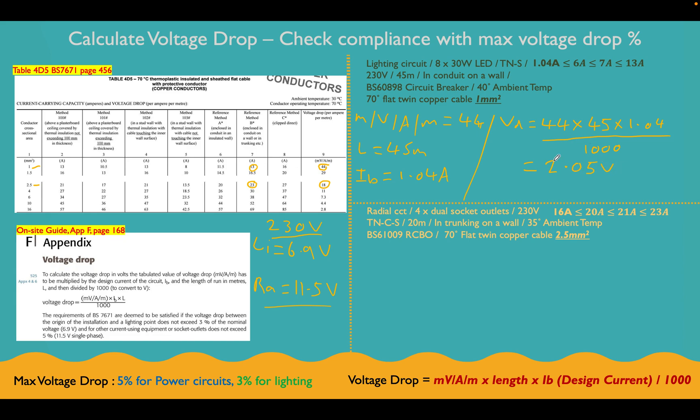Okay, so let's look now. Lighting circuit, the voltage drop for what we've designed here is 2.05 volts. Is that compliant? Yes, because it's lower than 3% of the supply voltage voltage drop. So it's less than 6.9 volts, so we're happy to say that that is a compliant circuit so far.